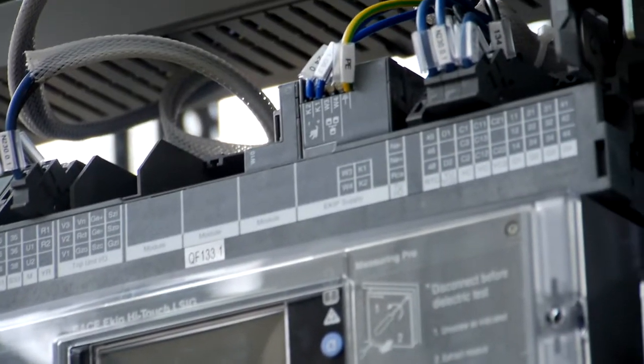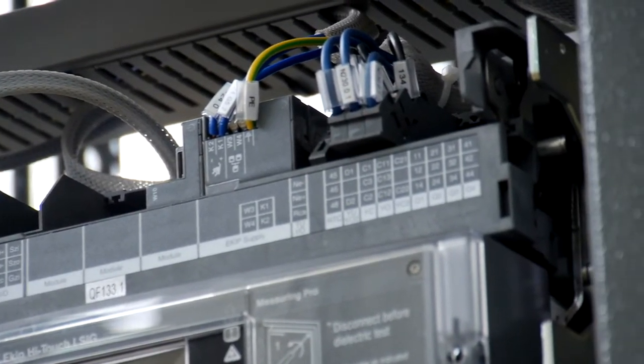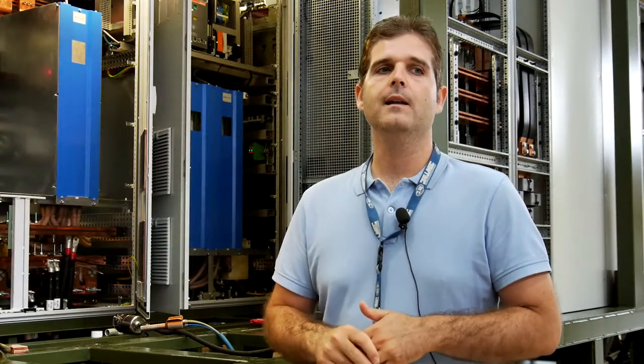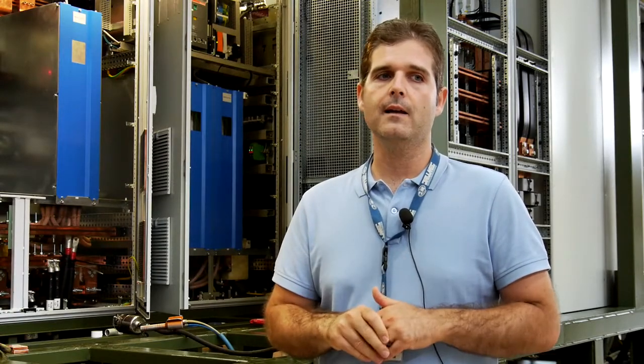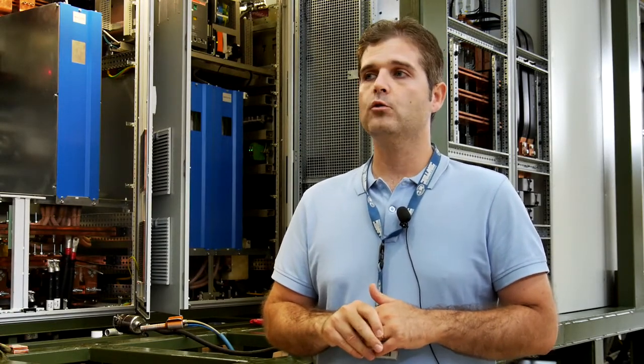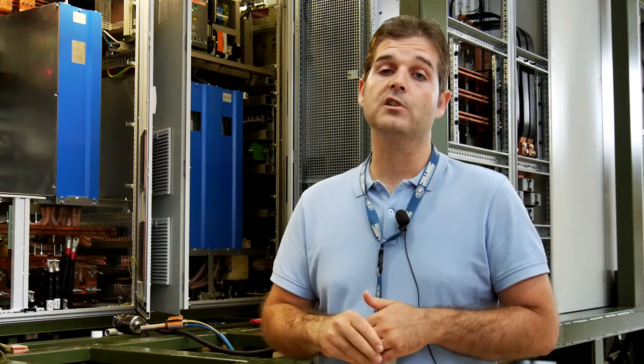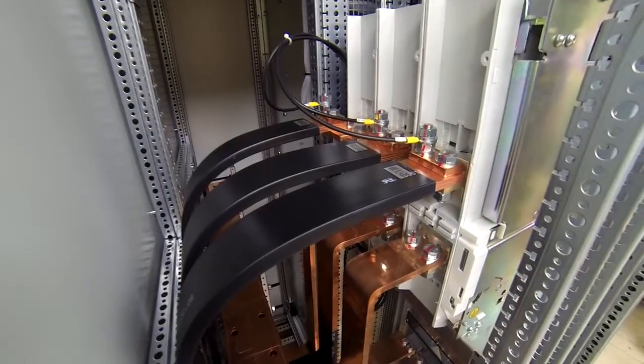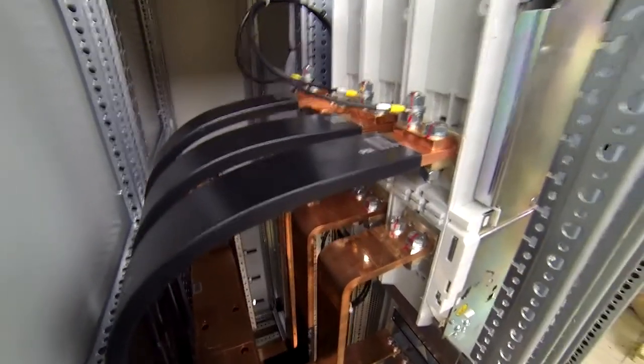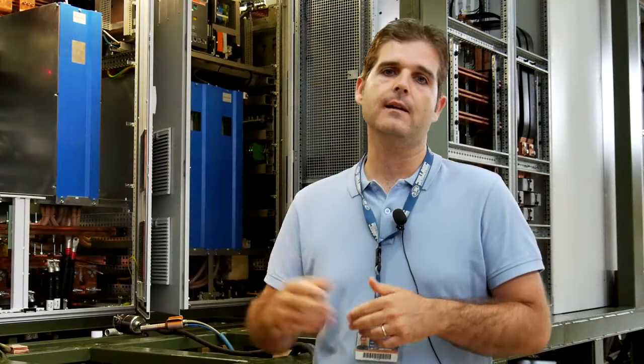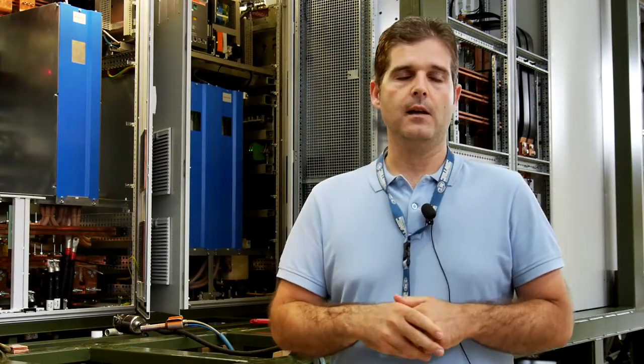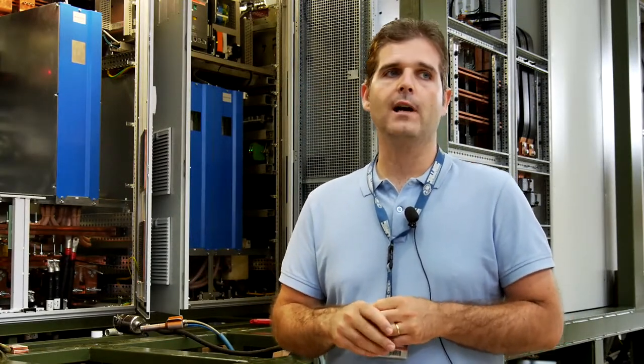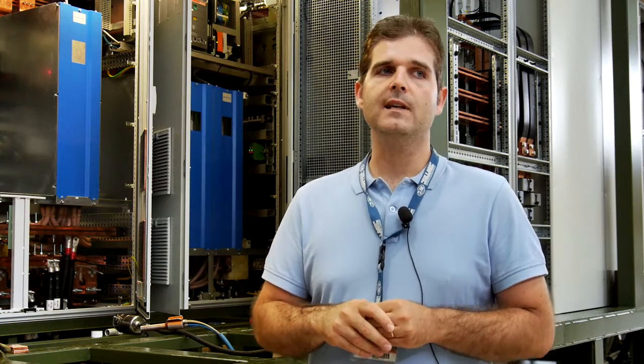The whole section that interfaces with the circuit breaker, or the man-machine interface, especially in the display and in the trip unit, has had a whole series of functions added that concern, above all, the analysis of the incoming voltage, the current, and the signals related to the circuit breaker - most importantly, certain functions dedicated to the management of the generators.